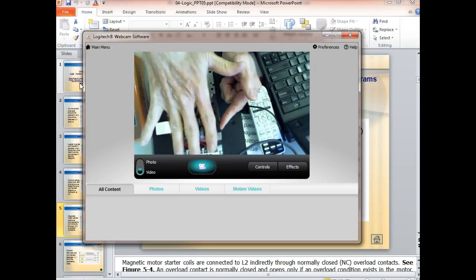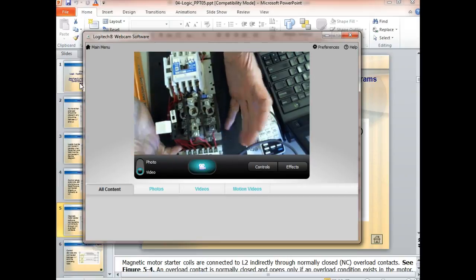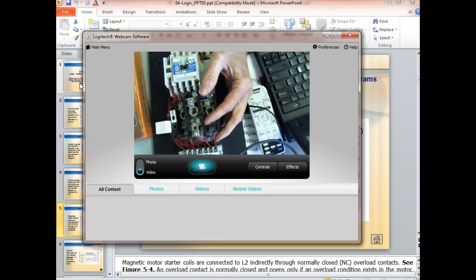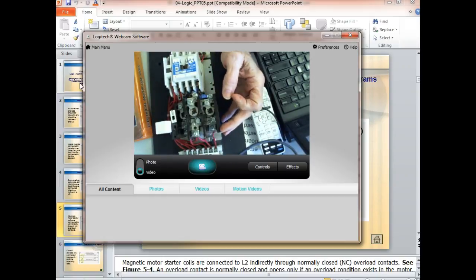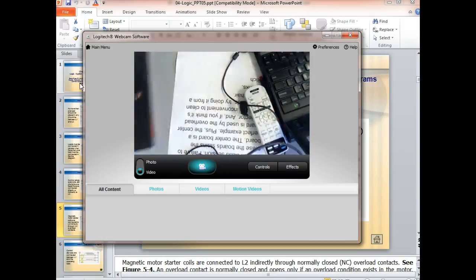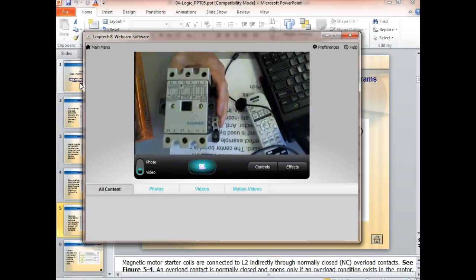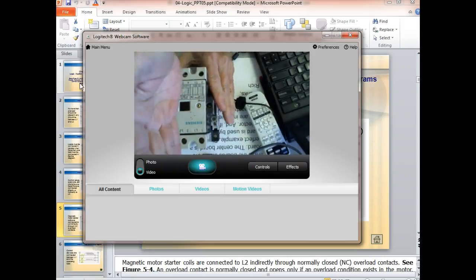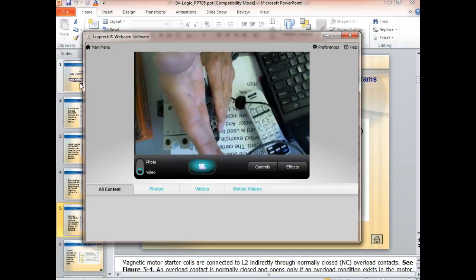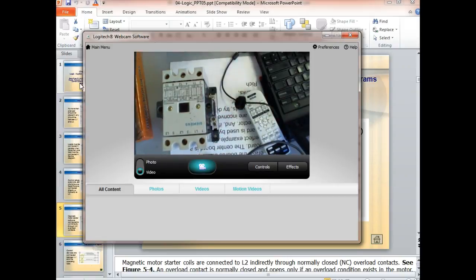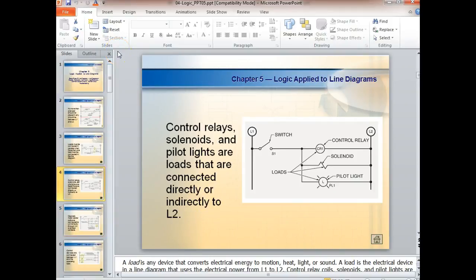So all the motor current runs through the overloads. If the motor comes in and pulls too much current, then it disconnects the control circuit. So this is a magnetic motor starter. This is a contactor. You understand the difference? The only thing that's allowed between L2 and the load is overloads. Everything else. So all the diagrams we look at are going to be like this. So here's the load. Here's L2. Here's the load. Here's L2. Here's the load. Here's L2. Nothing in here, right? You understand that?